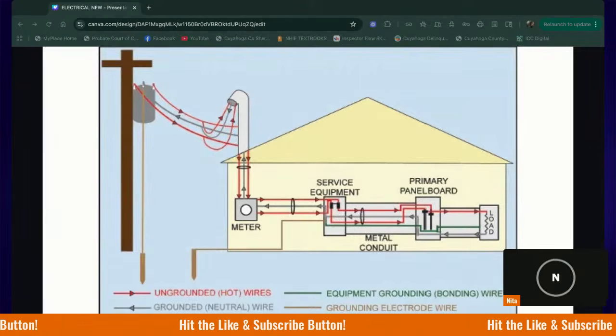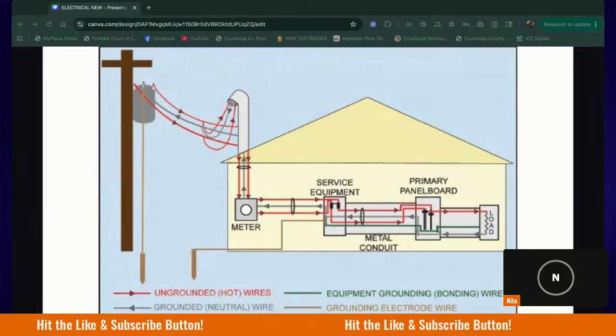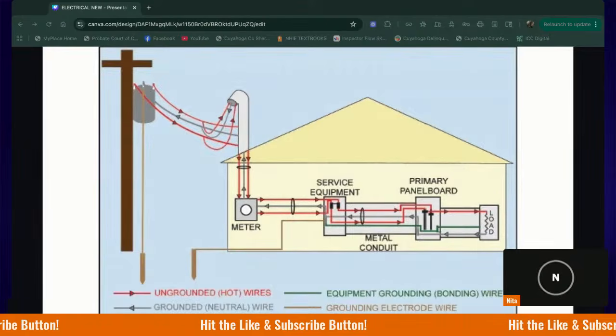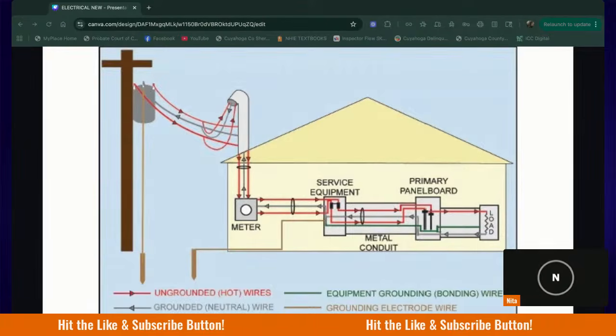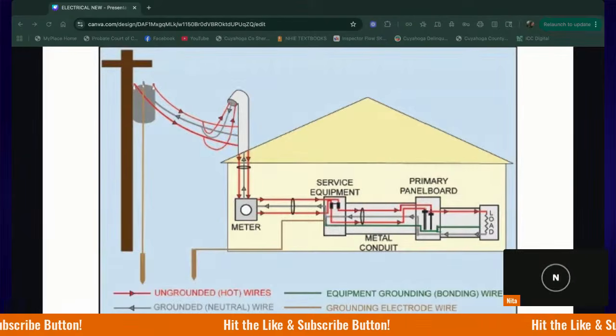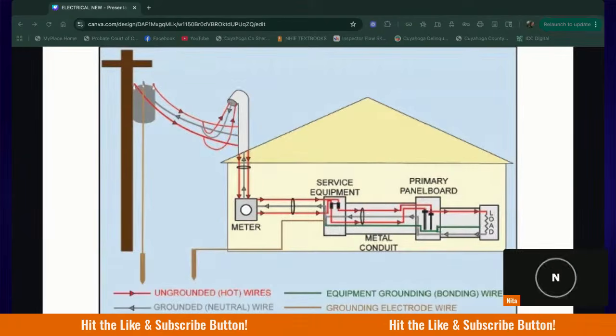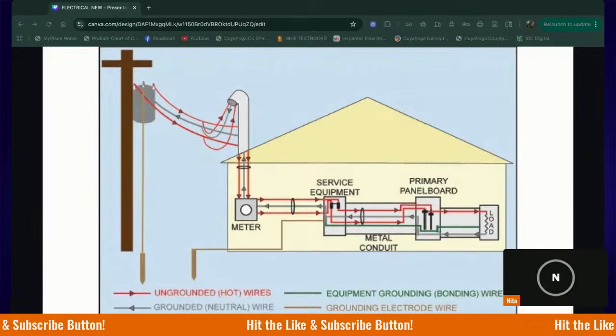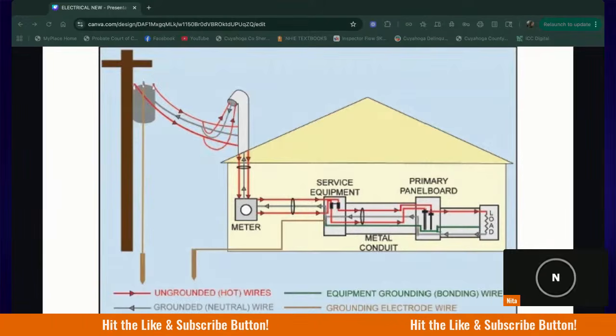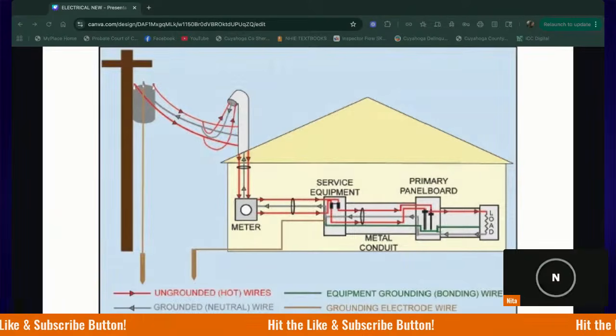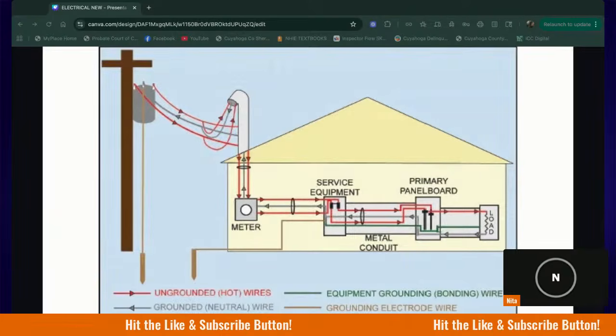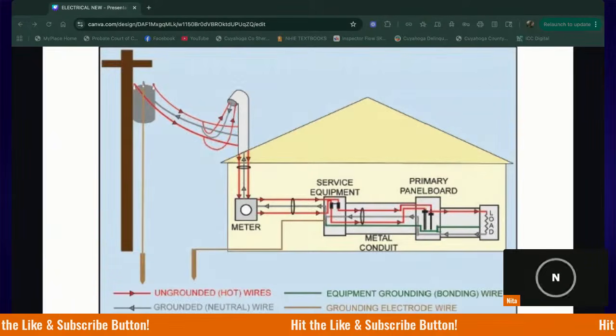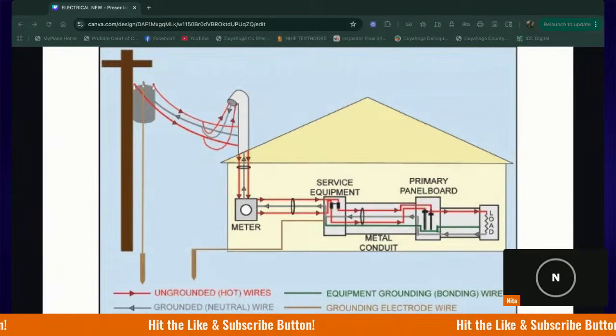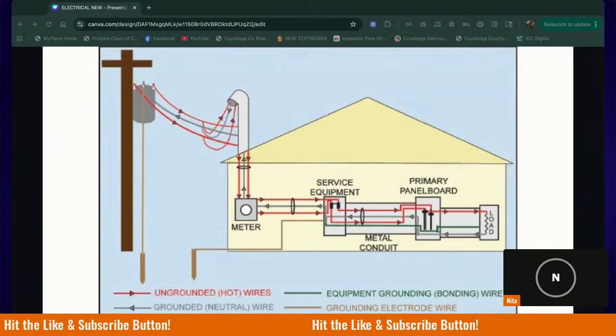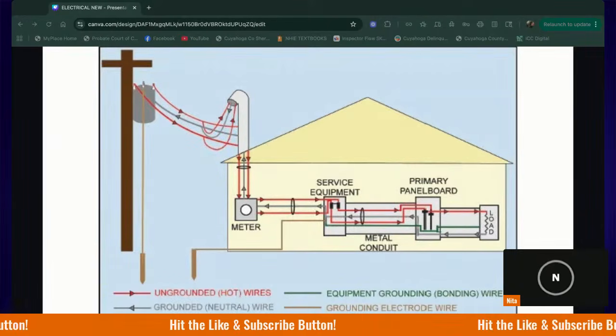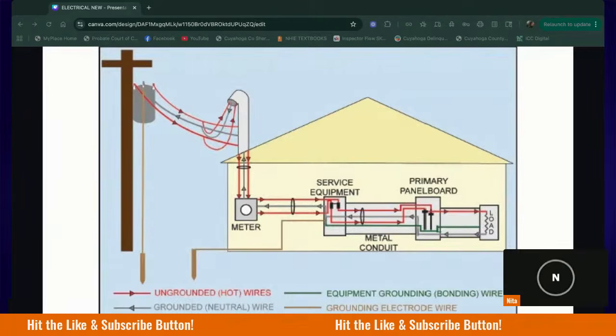I have a question. When we're talking about the service equipment, we're still on the outside of the house. That's not where we're flipping breakers and stuff yet, right? No, it is. That's why I said think panel, because you are tripping breakers inside in most cases. There are some places where those panels are outside, but in most cases, yes, you will be inside. If a breaker trips and you want to kill all the power to your house, you would go to the panel, which would have the main disconnect, which is considered service equipment.